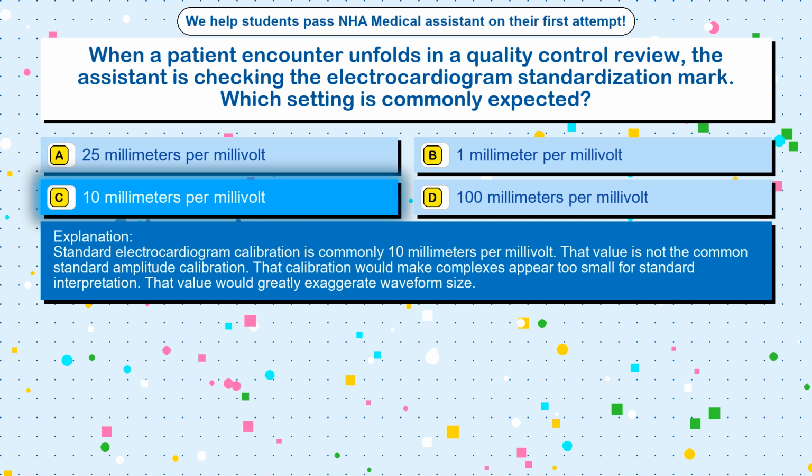That value is not the common standard amplitude calibration. That calibration would make complexes appear too small for standard interpretation. That value would greatly exaggerate waveform size.